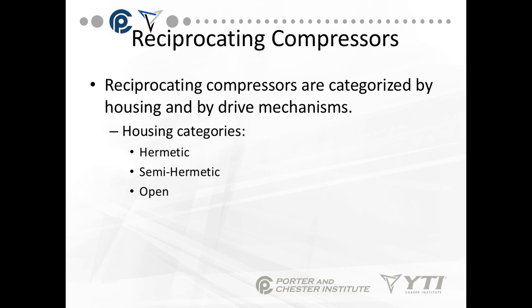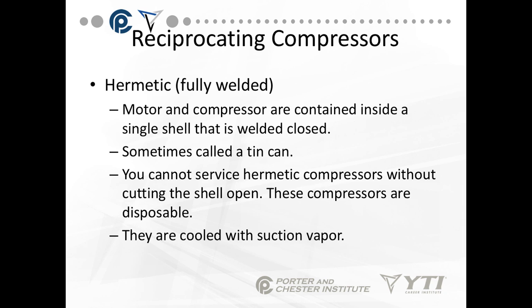Reciprocating compressors are categorized by housings and by drive mechanisms. Housing categories are hermetic, semi-hermetic, or open. The hermetic is fully welded — the motor and compressor are contained inside a single shell that is welded closed. You might hear it referred to as a tin can.